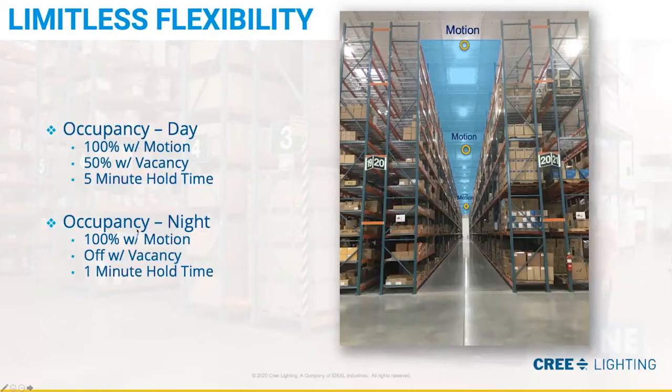schedule. In this example, you'll see most of the building here is made up of aisles. So this is a big warehouse, and they want to get those lights back down to their low dimming level as soon as possible after a fork truck has left the aisle. So during the day, after 5 minutes of inactivity, those lights are going to shut down to 50%. After hours, at nights and on weekends, they don't expect there to be any traffic. So if someone is in the facility, they want to get those lights off fast, get them into the off state instead of at 50% after 1 minute of inactivity.